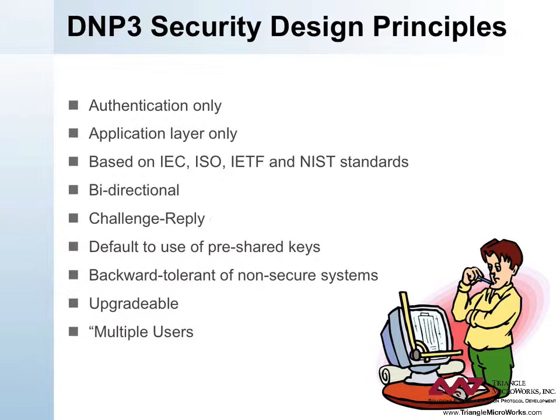This principle is dependent on how well the DNP3 implementation on the non-secure device handles unexpected messages. Upgradable Security Technology: security technology is always changing, so the mechanism permits the sender and receiver to identify which algorithms, data, and key sizes they are using, and change these in the future. The specification also requires that any implementation support a mode in which security is turned off on a per-device basis for upgrading purposes.